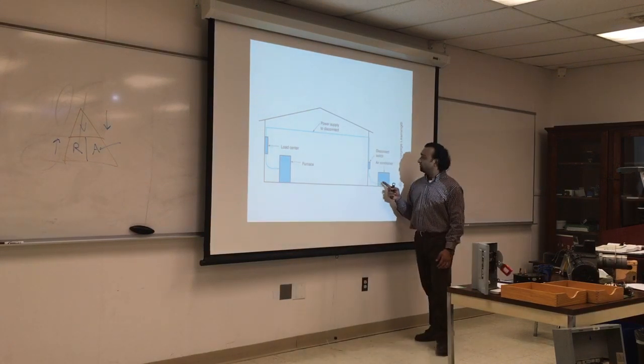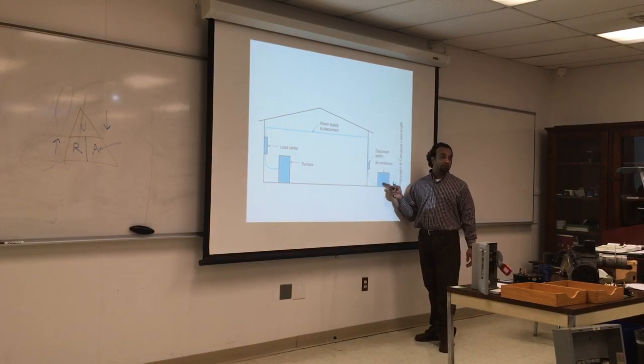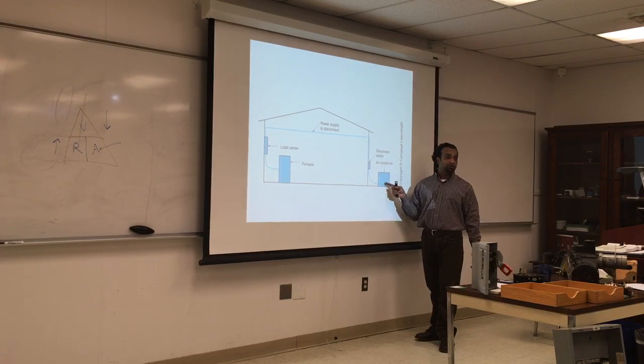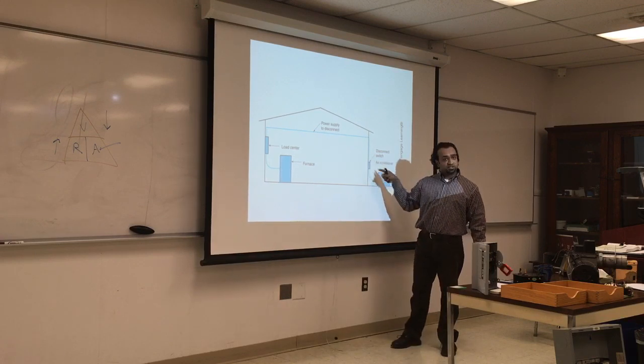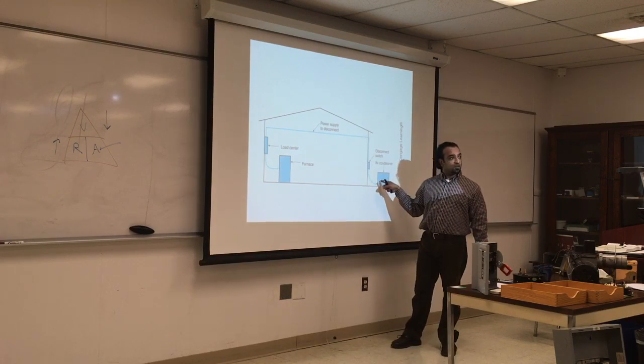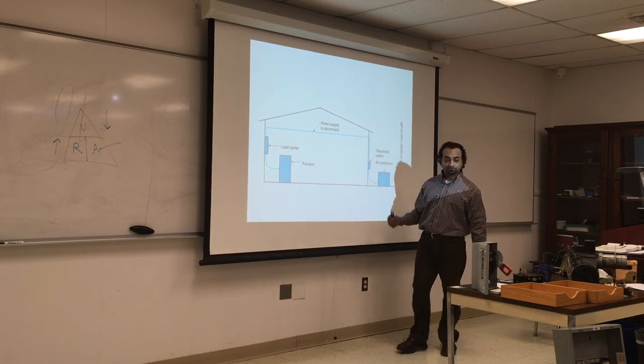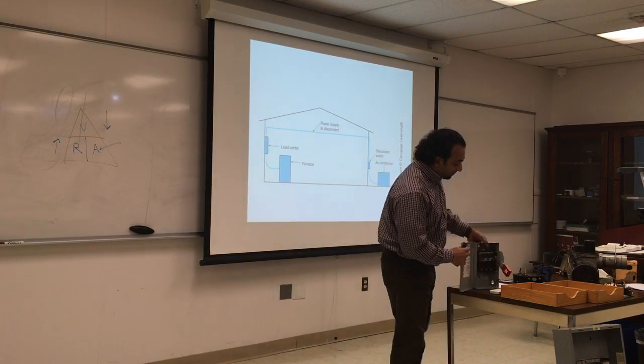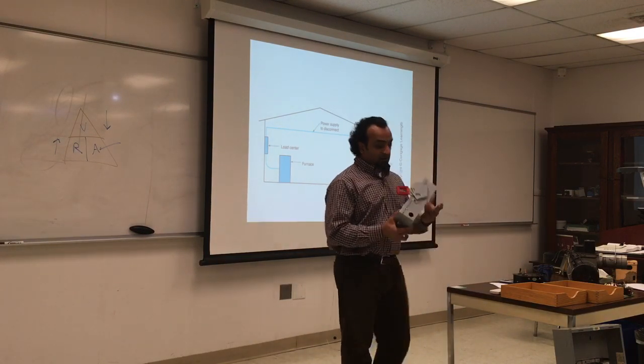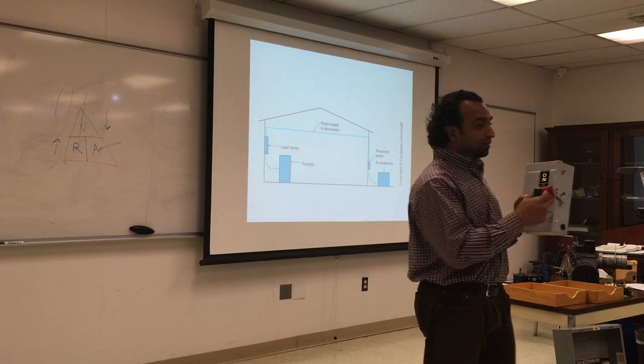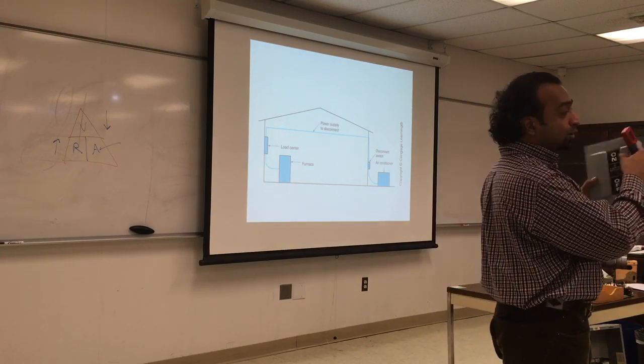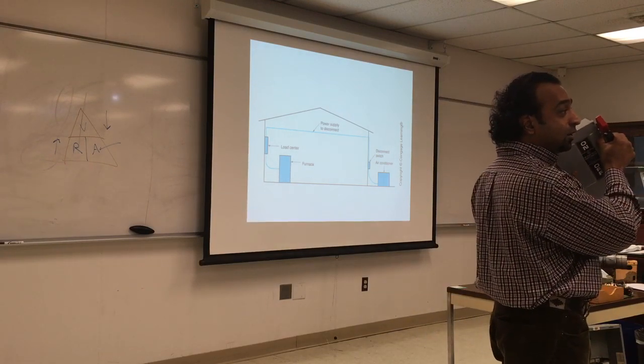The issue you will have is with the air conditioner, where you have your compressor and condenser outside. So you'll have a disconnect switch next to the equipment, so if somebody sees something on fire or it's making a lot of noise, they can come and shut it off. And again, remember from the first class ever, if you notice there are no holes here, so you cannot lock this in the on position.